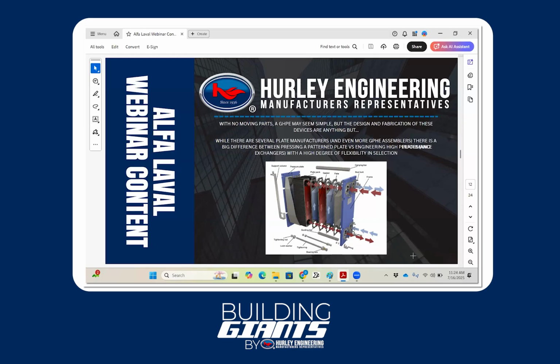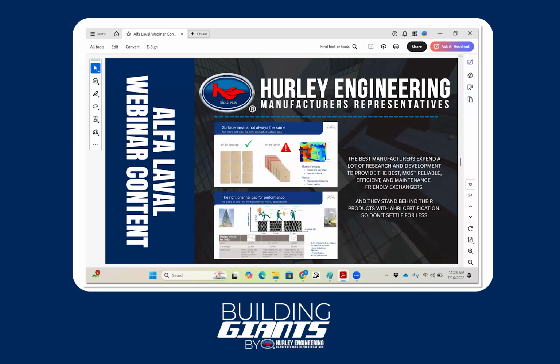Also, depending on the configuration, you'll have all your connection ports on one side, or they could be on opposite ends, depending on your application and if you need a specific type of flow pattern going through. Each of those plates will be suspended, and you'll have some type of gasket material, whether it's NBR or EPDM, depending on the fluids you're transferring. Make sure the manufacturer you choose gives you those options when looking at your materials.